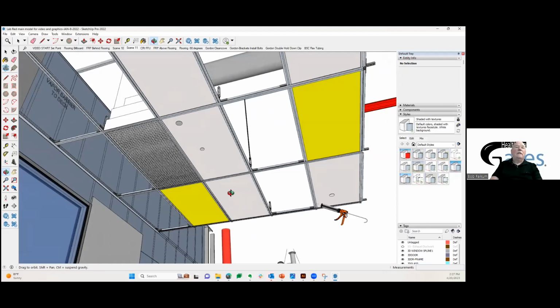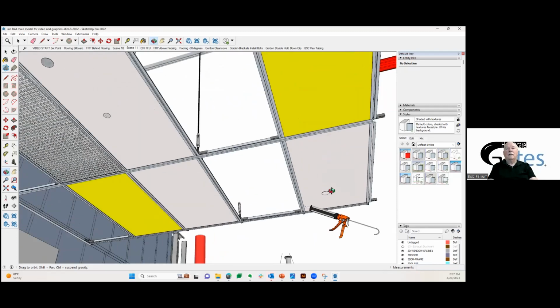On the bottom, I see a test port — we'll talk about that later — and a fire sprinkler, which should be flush, as you can see. Now, this very handy little caulking gun — many states demand it, not just require it, to make an airtight seal. You've already got a gasket in there, which at least gives you a dam. Do not use silicone — use a urethane based product. Silicone is what messed up the first space shuttle that went out, and that telescope.